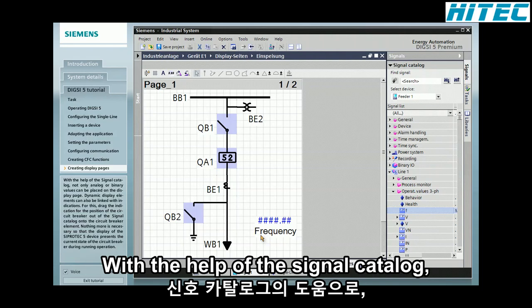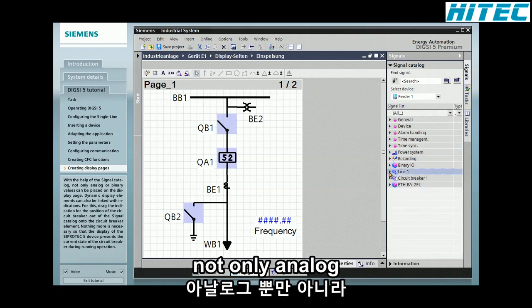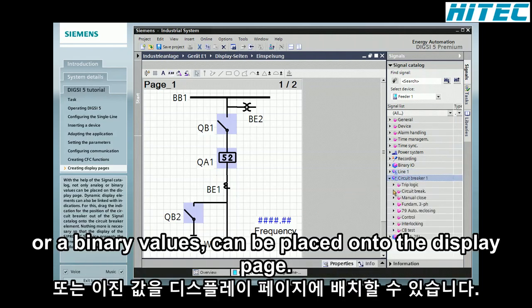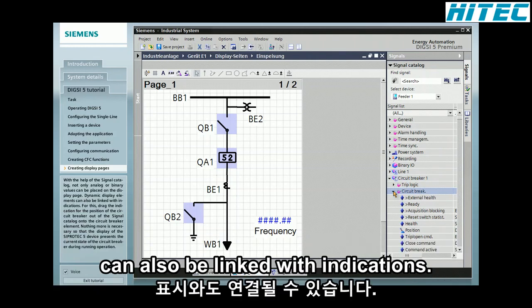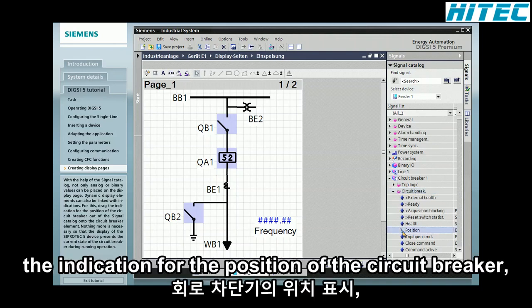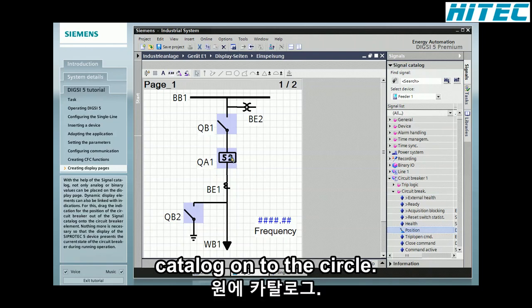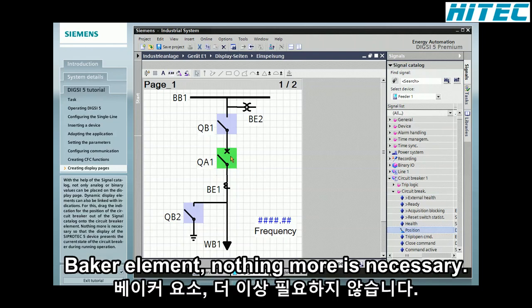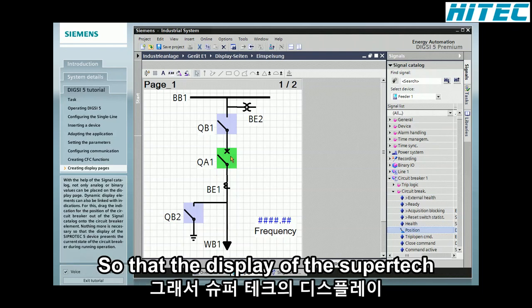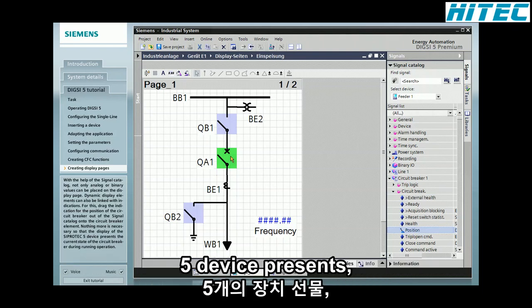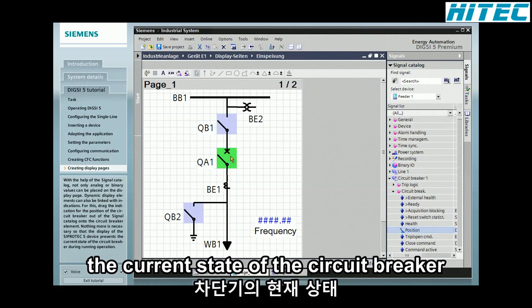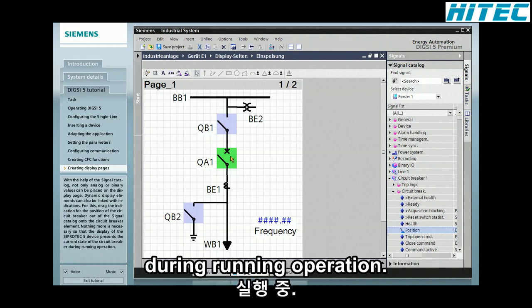With the help of the signal catalog, not only analog or binary values can be placed onto the display page. Dynamic display elements can also be linked with indications. For this, drag the indication for the position of the circuit breaker out of the signal catalog onto the circuit breaker element. Nothing more is necessary so that the display of the SIPROTEC 5 device presents the current state of the circuit breaker during running operation.